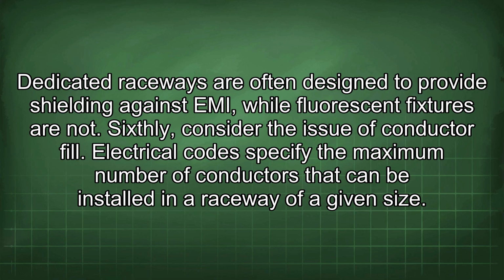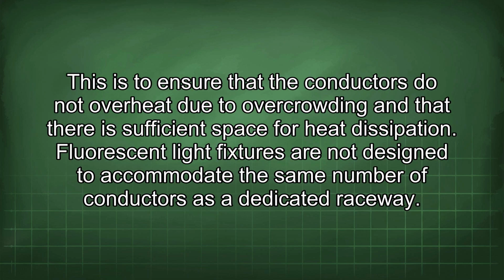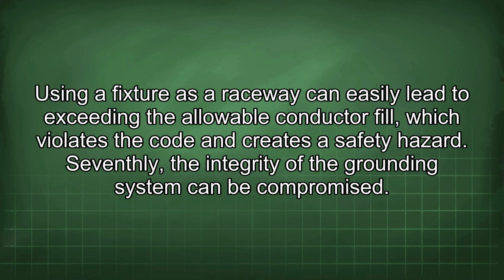Sixthly, consider the issue of conductor fill. Electrical codes specify the maximum number of conductors that can be installed in a raceway of a given size. This is to ensure that the conductors do not overheat due to overcrowding and that there is sufficient space for heat dissipation. Fluorescent light fixtures are not designed to accommodate the same number of conductors as a dedicated raceway. Using a fixture as a raceway can easily lead to exceeding the allowable conductor fill, which violates the code and creates a safety hazard. Seventhly, the integrity of the grounding system can be compromised.